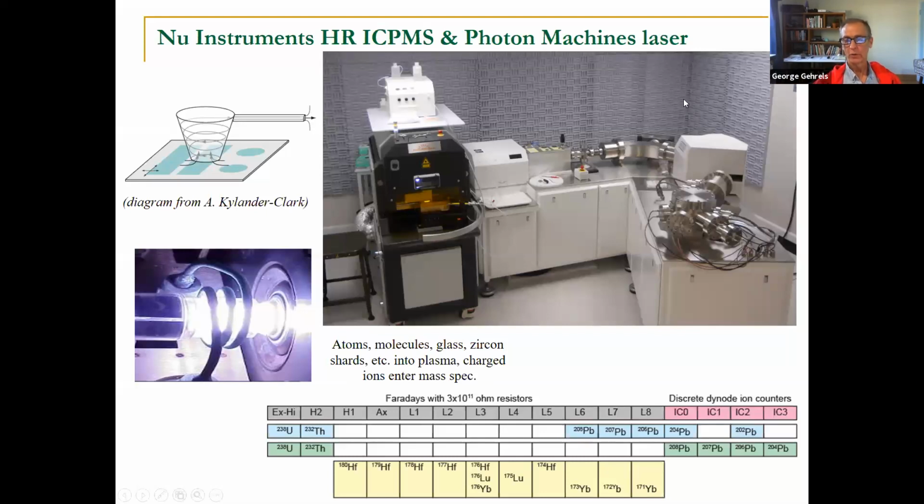After 20 years of doing this routinely, you buy a laser, you buy a mass spectrometer, and you're the one that has to figure out how to get those two to work together and talk to each other. They're not made by the same company. So the sample is analyzed as the laser beam pulses down onto the sample surface. Where you're hitting that material, it's carried in helium gas. It goes through the tube into the mass spectrometer.